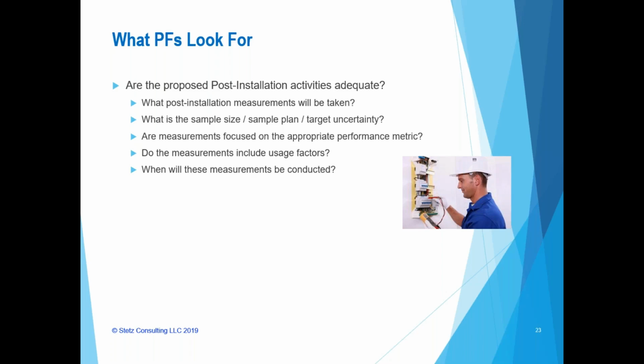If you measure chiller demand on a 90-degree day, then change out your rooftop unit, and a couple months go by and now it's 60 degrees, and you take a KW measurement, the KW is going to be less because you haven't corrected for weather. So there could be effects that need to be considered.